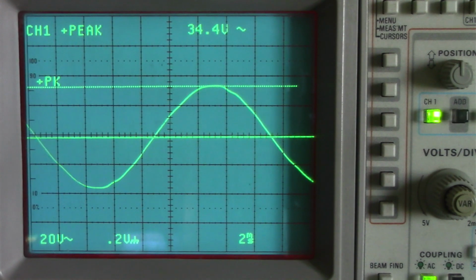Now we can turn on the current, which is displayed on channel 2. You'll notice that the current is not symmetrical. It has peaks occurring at the voltage zero crossing. Another way of saying that is there's a 90-degree phase shift between the voltage and the current. Keep in mind that there is no load on this transformer at this particular time.